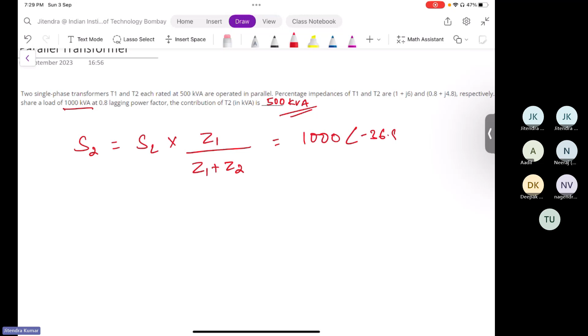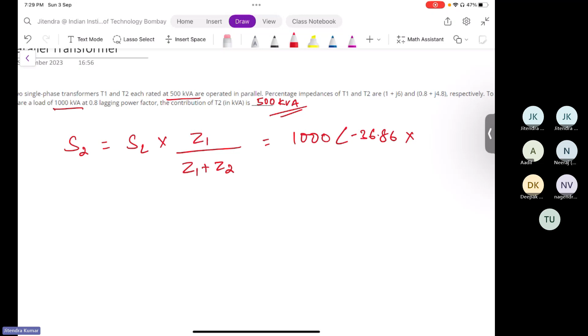So SL is 1000 angle minus 36.86, into Z1. Now for percentage impedances, since both are 500 kVA, we don't need to change per unit values. If the kVA rating of the other transformer had been different, you would need to change the per unit impedances, but since both are the same kVA rating, you can go ahead with whatever is given.